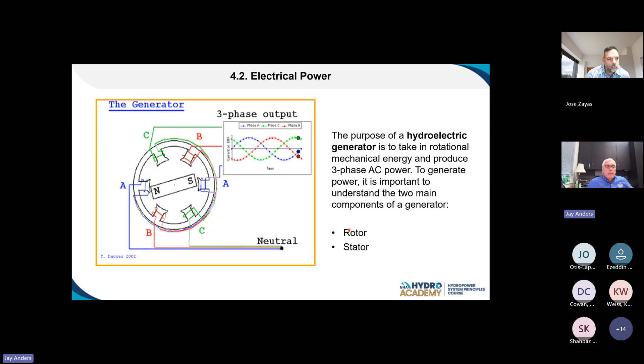Another key piece of it is the excitation system. We talked earlier about the governor being used to control the speed of the unit, ultimately controlling the number of megawatts that the unit is able to supply to the system. Well, the same thing, we have this idea of the excitation system. It's used to control the voltage. The voltage then, what it controls is the kilovolt amperes, my kVAR, my reactive power.